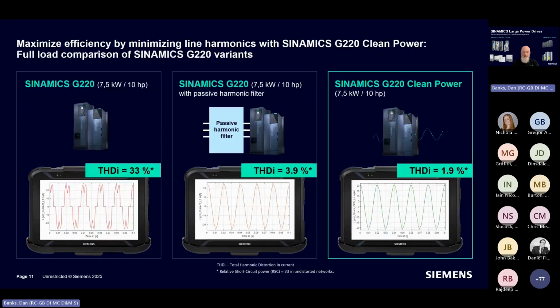To give you a comparison, the G220 drive range exists in clean power and non-clean power versions. With the non-clean power version, you might be looking at a THDI current distortion percentage of 33%. We could fit that drive with a passive filter, getting down to about 4%. But the clean power drive comes in at 1.9% in this case, and that's a measured number, not calculated - we've got a real product out in the world and we've measured it. So you can see it's really clean. It's really going to help you get that compliance, drop your noise levels down, and bring the reliability of your equipment up.